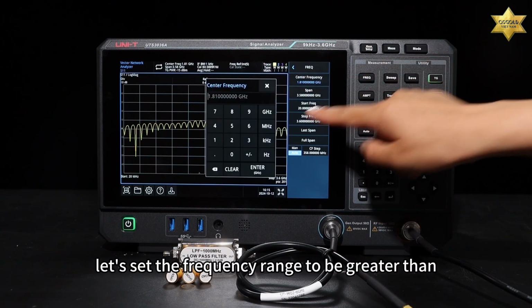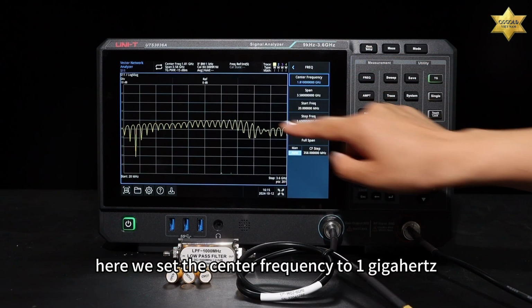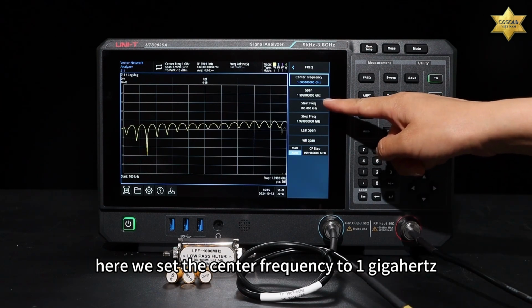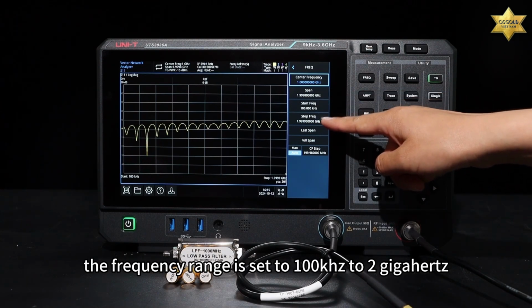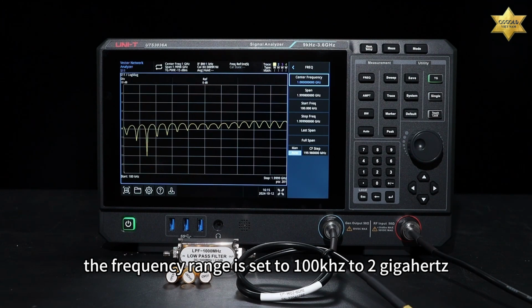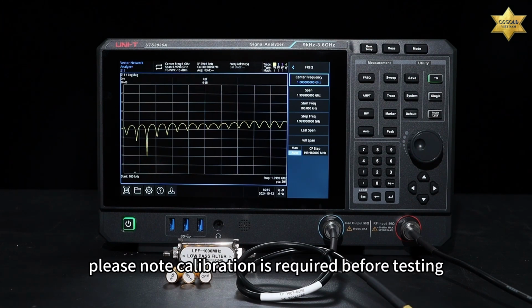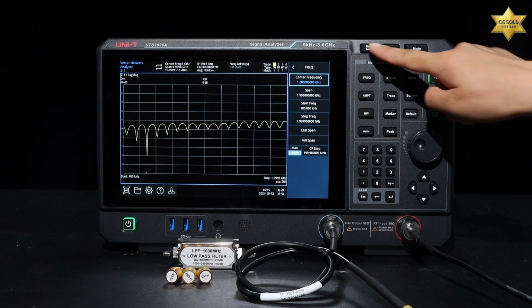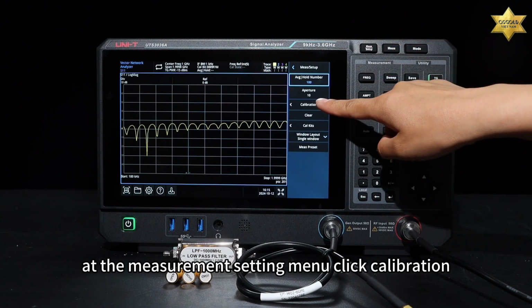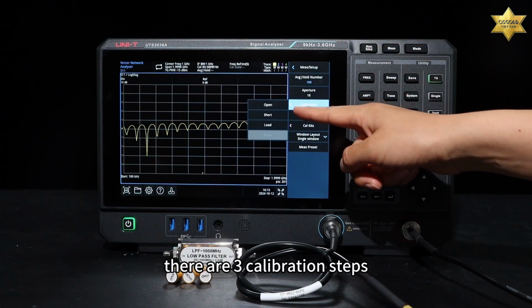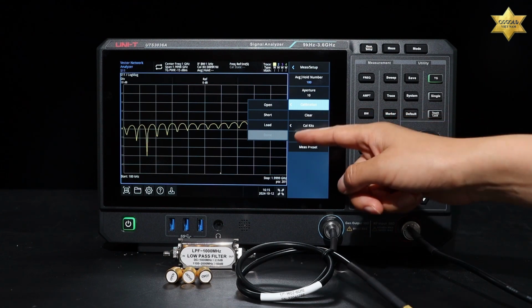Let's set the frequency range to be greater than 1 GHz. Here we set the center frequency to 1 GHz. The frequency range is set to 100 kHz to 2 GHz. Please note, calibration is required before testing. At the measurement setting menu, click calibration. There are 3 calibration steps.